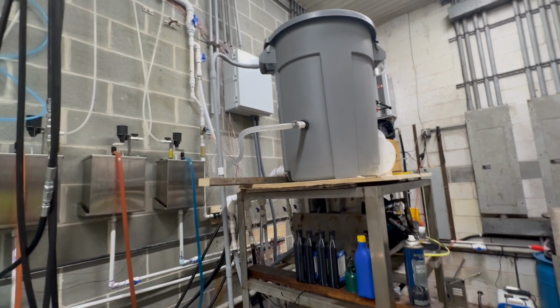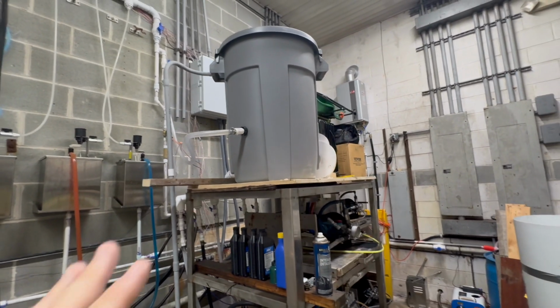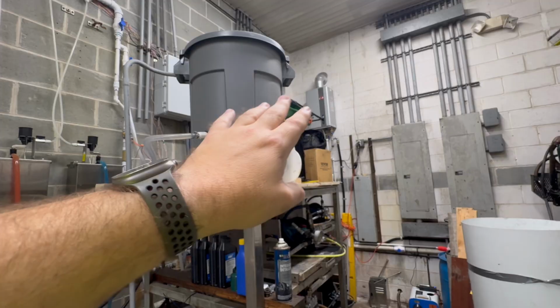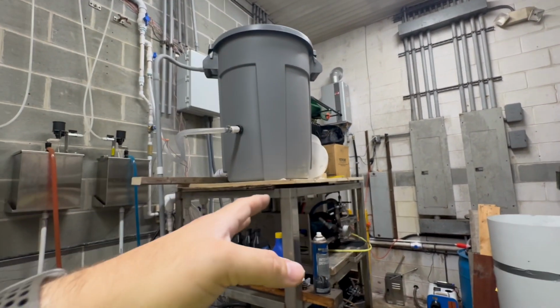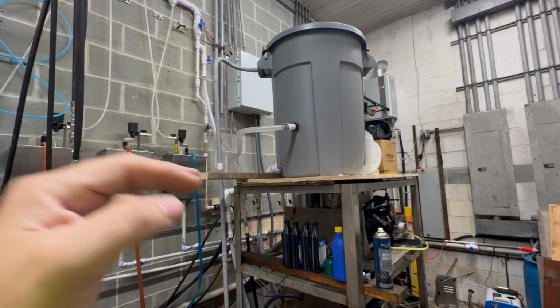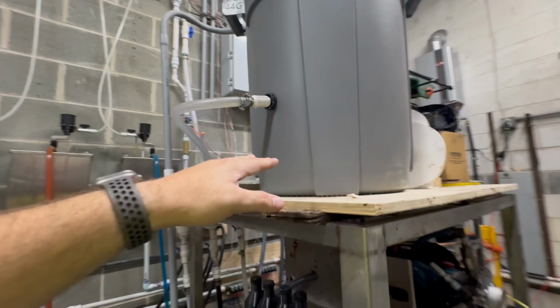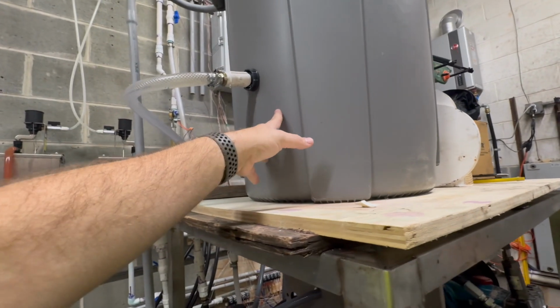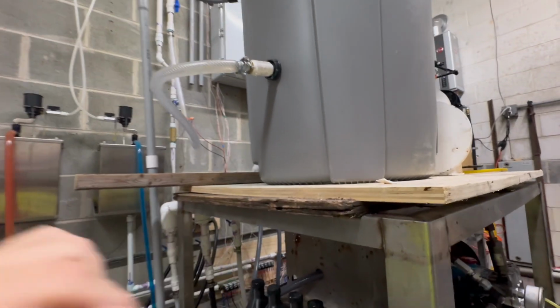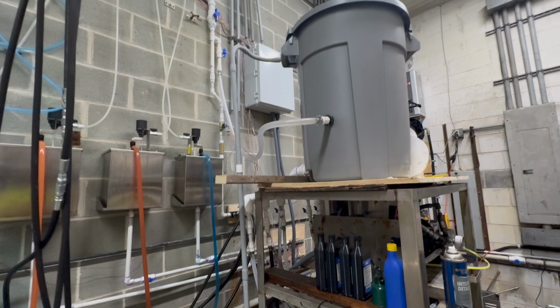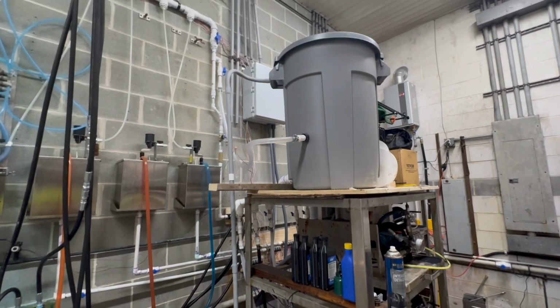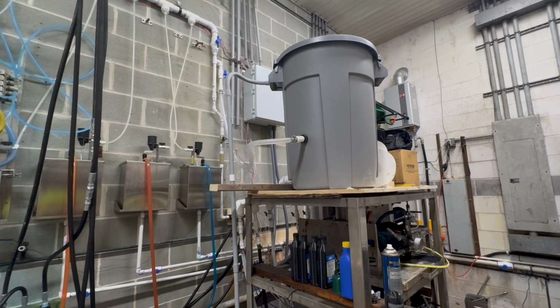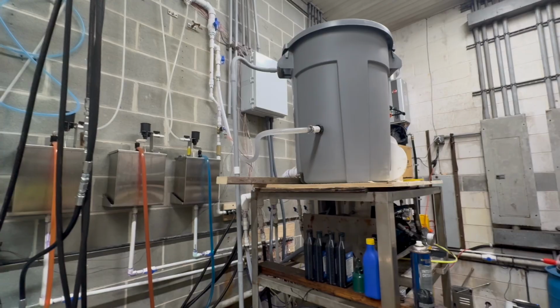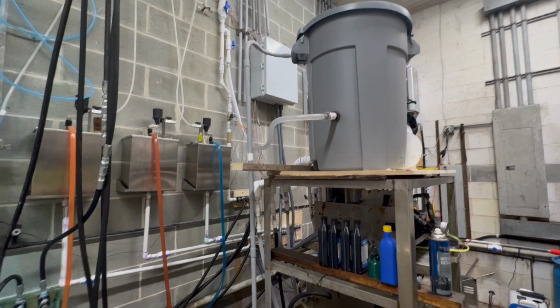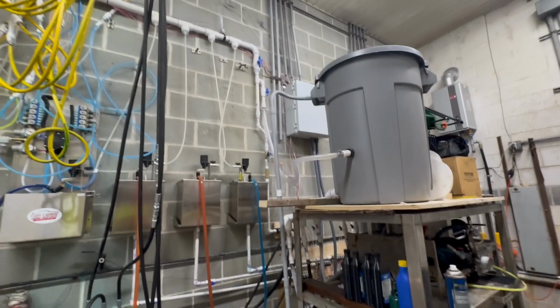Essentially, if we get really busy and I'm having flow issues on hot water, because the hot water heater has to slow down a little bit to heat to 110, this backup basically means your water might get cold in the bays or cooler, but I'm never going to starve the pumps. I'm not going to run the pumps dry. It's a safety, it doesn't get used unless I'm really busy — it'll kick on once in a while, barking on and off, but it's barely causing customer impact.